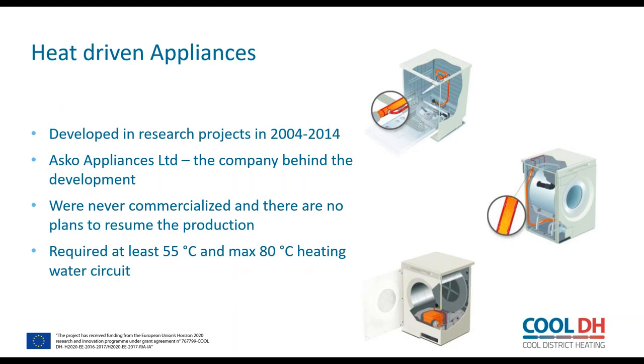So what are heat-driven appliances? They are machines, dishwashers, washing machines, and tumble dryers, that have heat exchangers integrated into the machines themselves. The heat exchangers are in turn connected to the building's district heating substation through a heating water circuit similar to radiators. And in that way, the heat exchangers enable the process water in dishwashers and washing machines and the process air in tumble dryers to be heated partly by thermal energy instead of electricity. So why do we want them then?